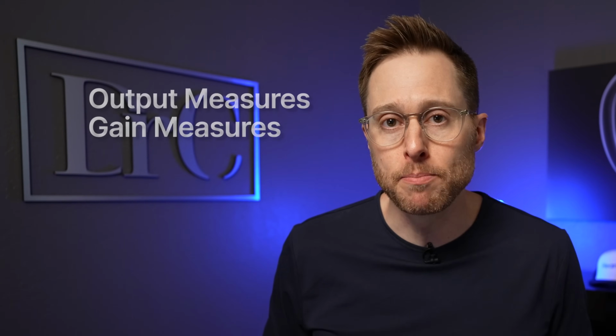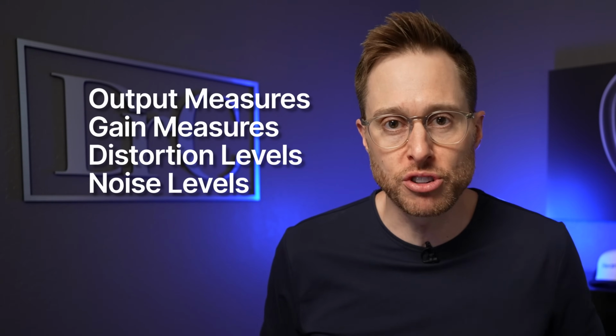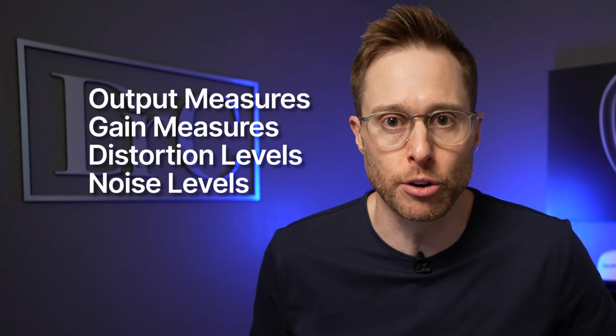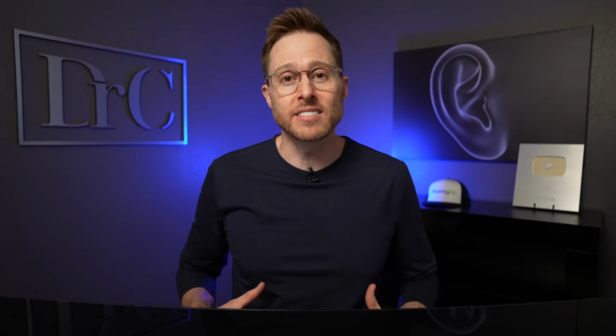Several of these hearing aid performance characteristics include output measures, gain measures, distortion levels, as well as noise levels of the hearing aids. If any of the diagnostics inside of these 4 categories are not within the tolerance ranges, then we know that there is something starting to go wrong with their hearing aids. And we can take care of the problem before it becomes a problem. That's why it's so important to have a hearing care professional who's going to be doing this preventative maintenance for you and running these different diagnostic tests, so a small problem doesn't grow into a big problem that negatively impacts the reliability of your hearing aids.